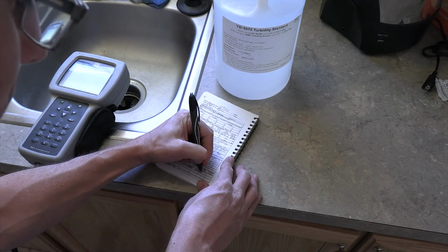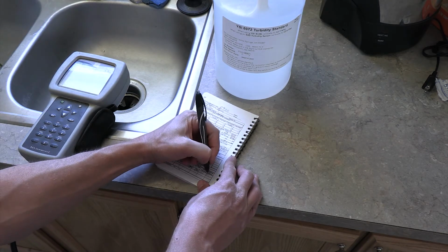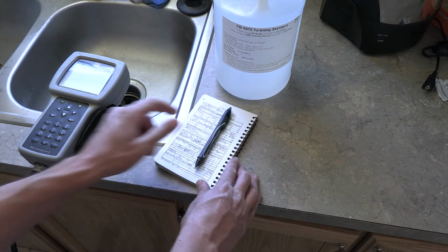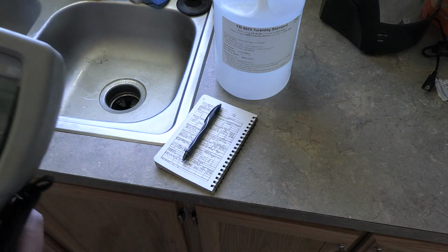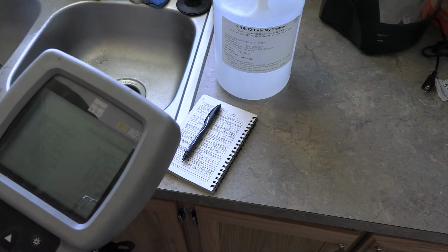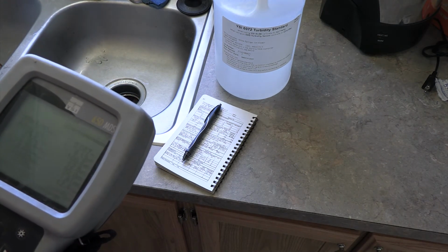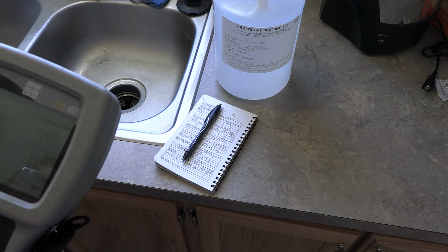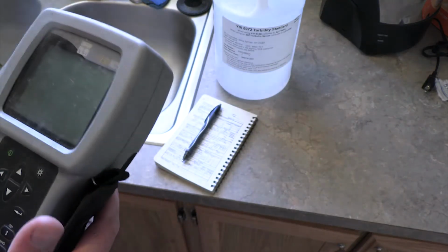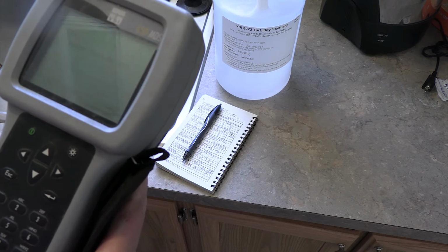Okay, so 13.1, and then we'll go 12.7. But it is important to go ahead and do this 0.8 calibration, because it will go negative. Well, let's go ahead and check it and see where it goes with the DI water. So let's press enter again, and we'll go back to one more 1 point calibration. This time we'll use 0.8.